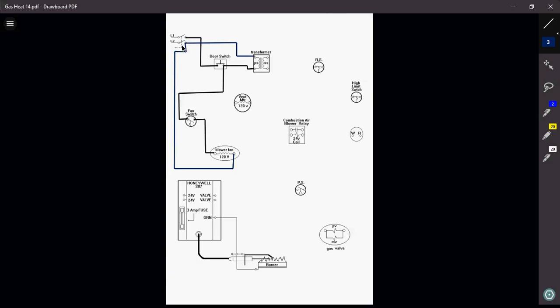Okay? So, we completed those two circuits right there. But I still got one more to do. I got my vent motor. That's a load. But I have to have something there that's going to control it, right? Source, path, switch, load. Okay, so where's my switch that's going to control my vent motor? Looking at the diagram. If you said the combustion air blower relay, you're correct. That is your control device that's going to start and stop that motor.